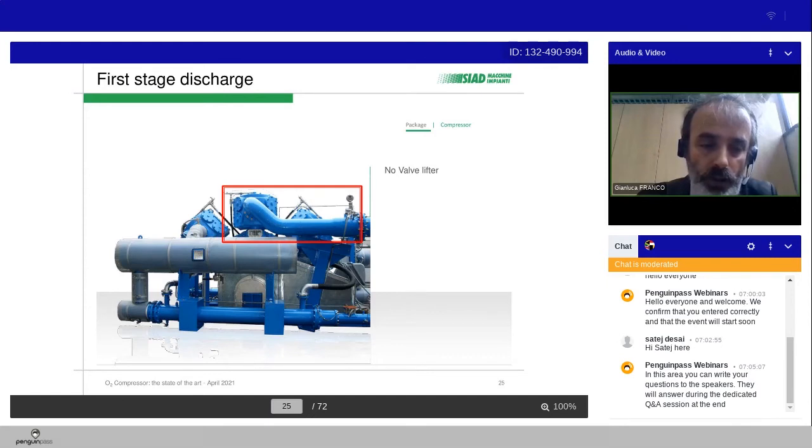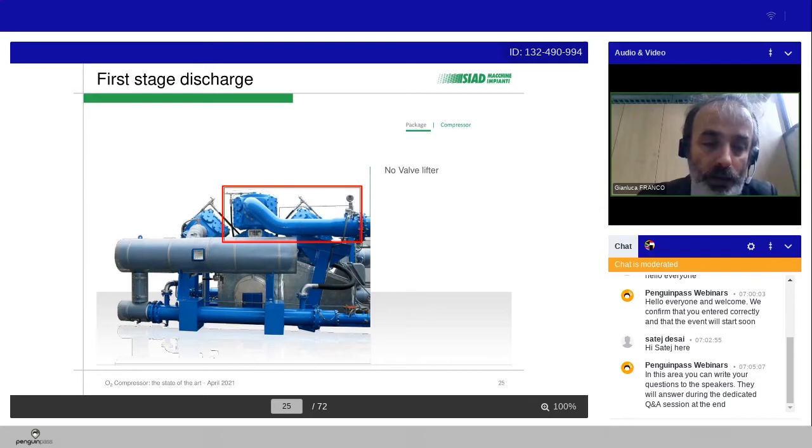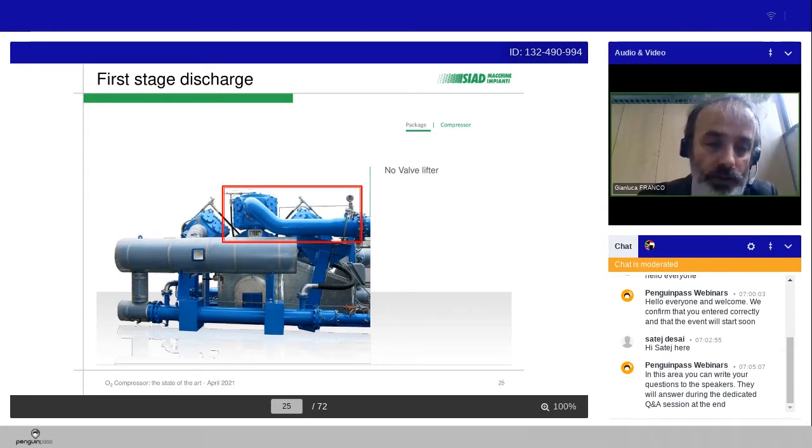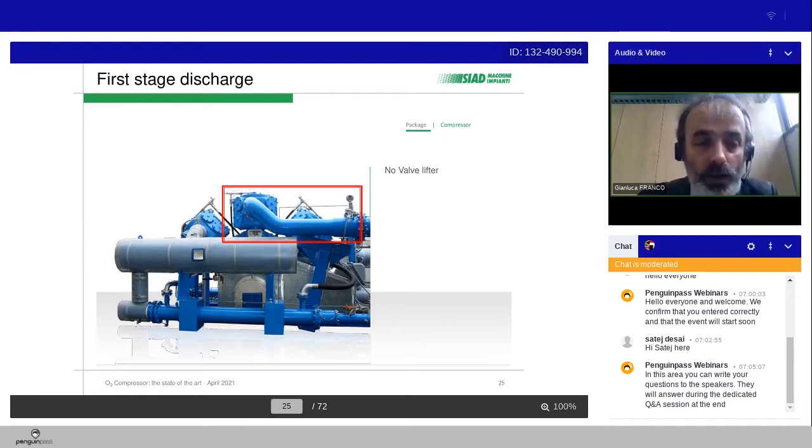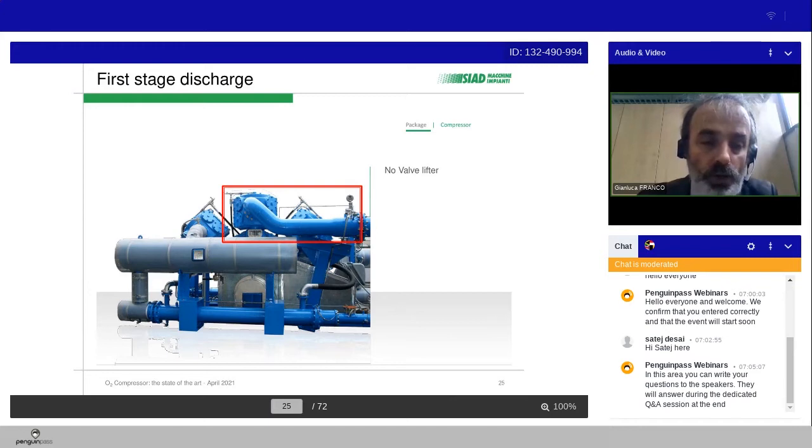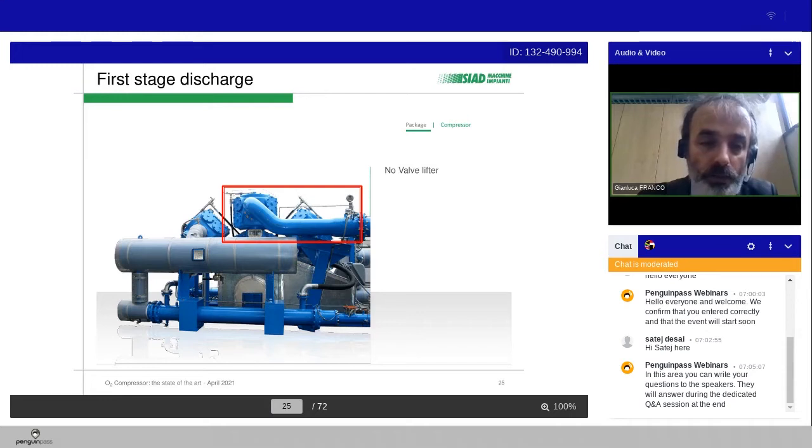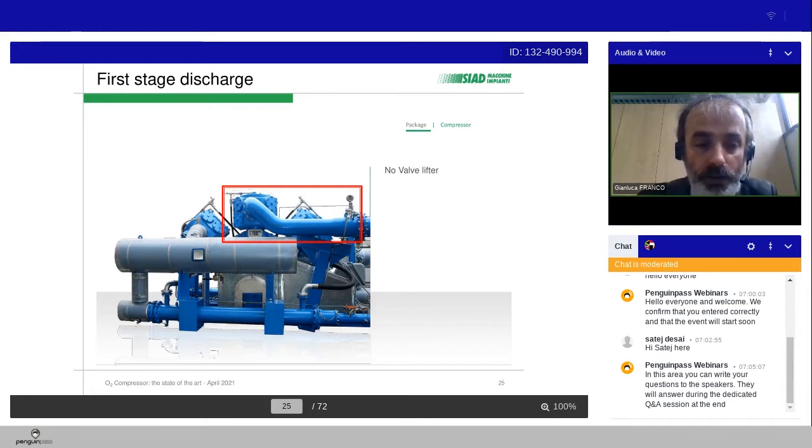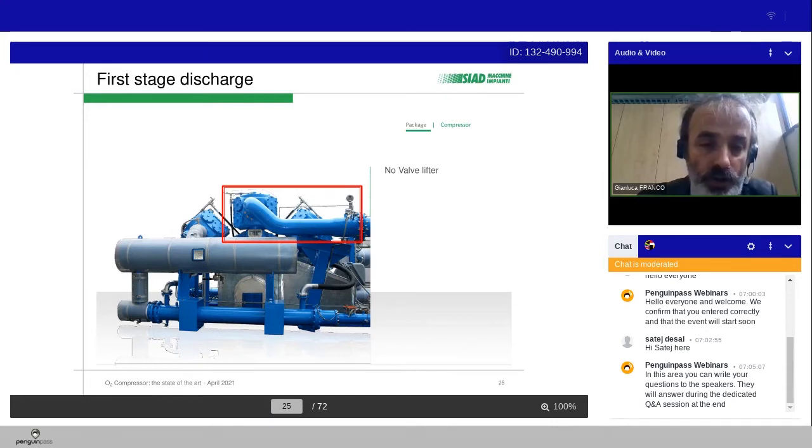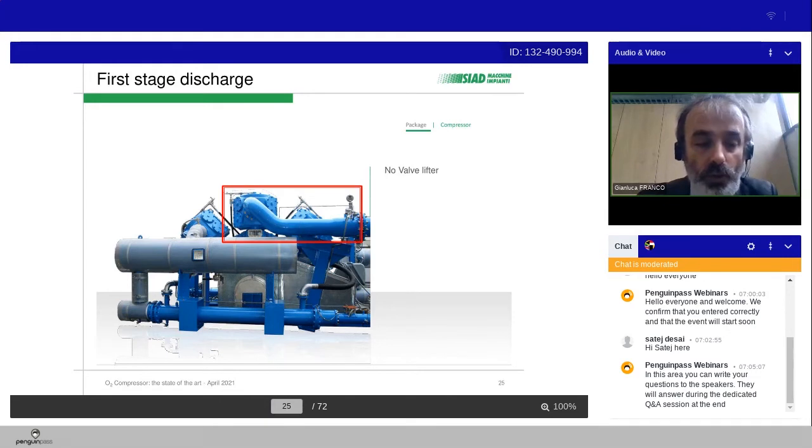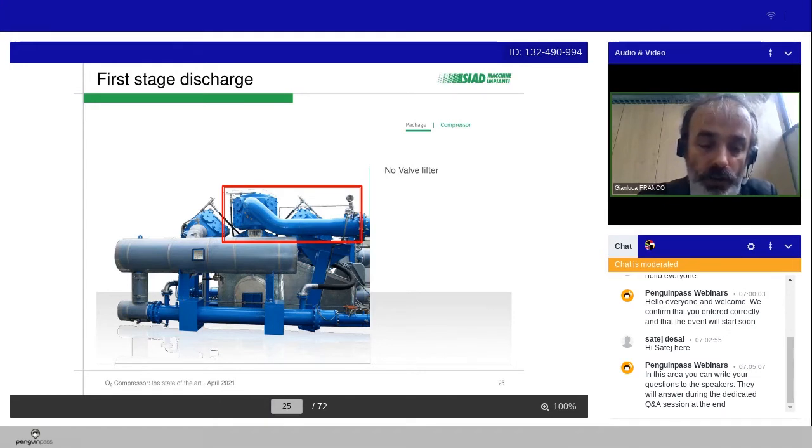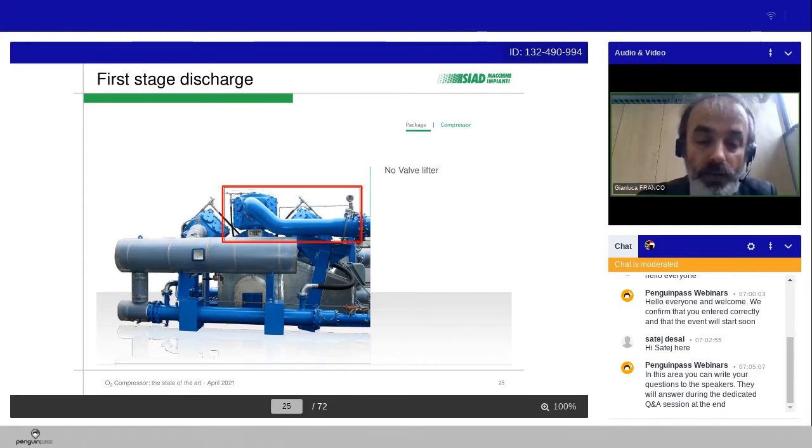Speaking with the reciprocating compressor, one of the most added value of these machines is that you can regulate the flow with different systems according to the customer needs. With the oxygen compressor, the flow regulation cannot be adopted with valve lifter because the valve lifter will increase the temperature during the unloader step, increasing the risk of combustion processes or ignitions. So the regulation is made by a recycle valve.